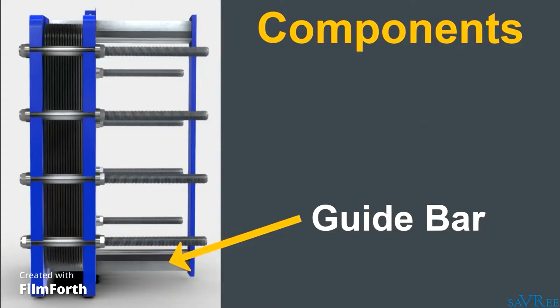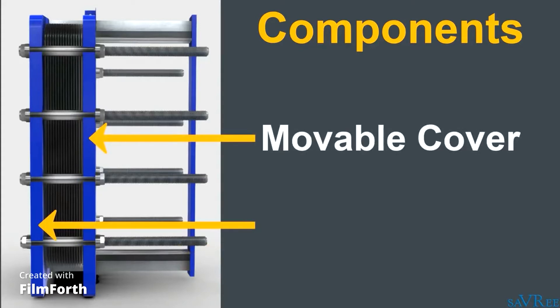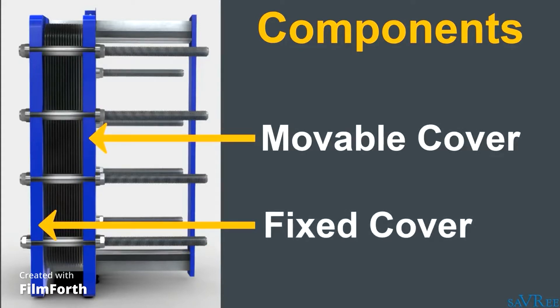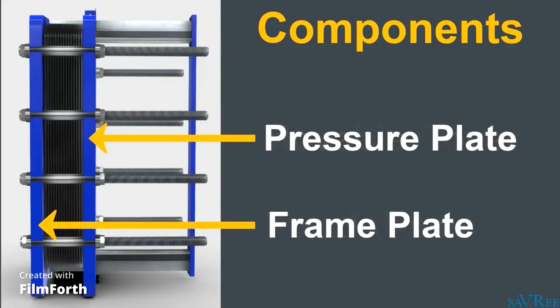The final components of interest are two covers at opposite ends of the plate stack. One cover is moveable, whilst the other is fixed. The moveable cover and fixed cover are also sometimes referred to as the frame plate and pressure plate. Note that the inlets and outlets are mounted to the fixed cover only.